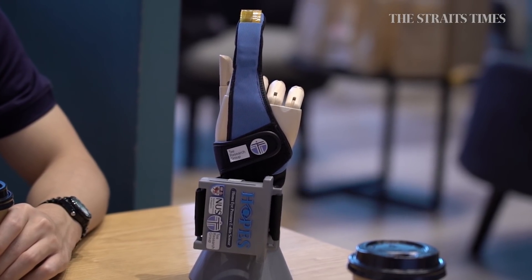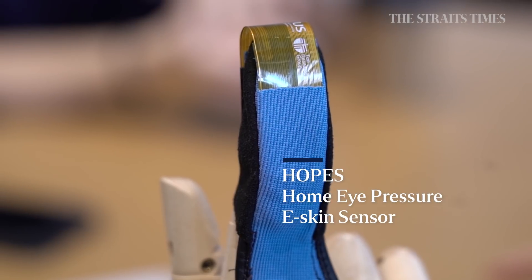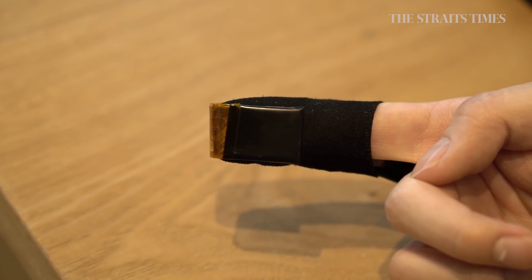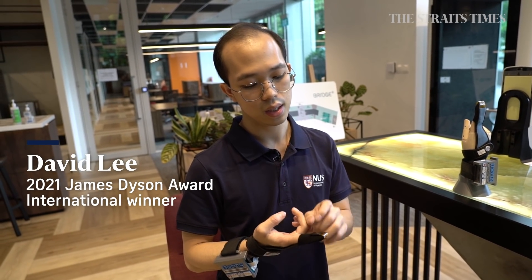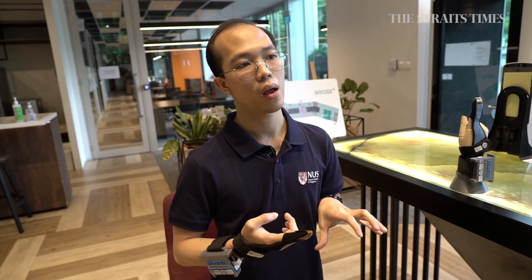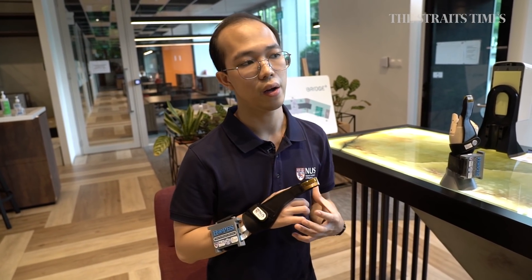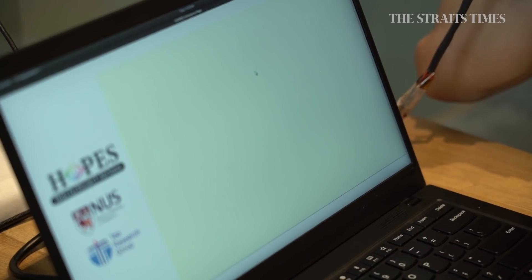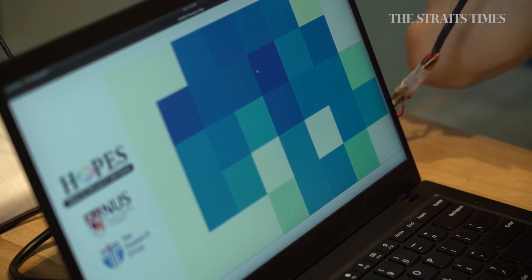HOPES is the Home Eye Pressure e-Skin Sensor. It basically consists of a tactile sensor mounted on the fingertip, connected to a set of electronics. When you press the sensor against the eyelid, it captures the pressure map of the patient's eye, and uses AI to understand the eye pressure. Darker colored squares on the reading indicate higher eye pressure, often associated with glaucoma.